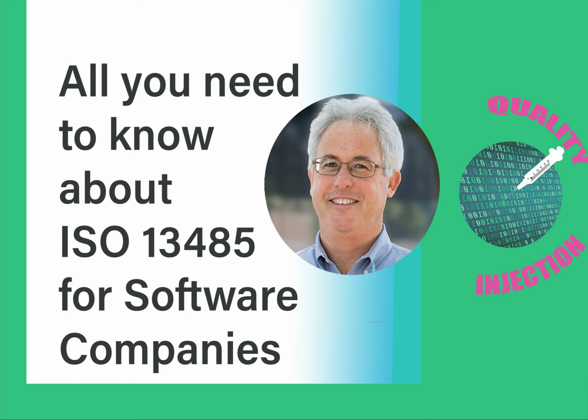The danger is, unlike gaming and some rapid prototype, in medical device, we have to keep our documentation in sync no matter how fast we do our sprints. And so I've seen some companies that do these very quick 2-week sprints, and they lose track of the documentation, and that's not acceptable. And so I think you can use some of these new innovative software development processes, but you must keep the requirements in sync.